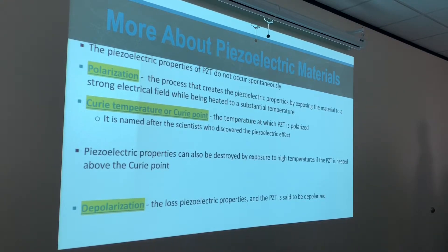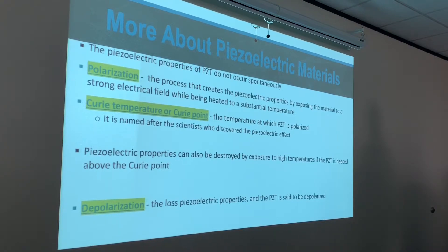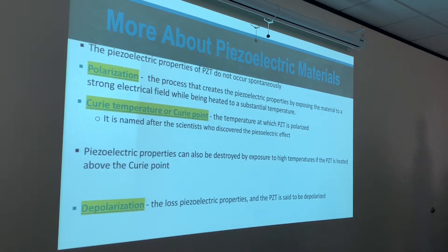Piezoelectric properties can also be destroyed by exposure to high temperatures. If the PZT is heated above the Curie point, the PZT becomes non-functioning — that's why we're not allowed to put transducers into an autoclave. An autoclave is what's used to clean surgical utensils. Depolarization is the loss of piezoelectric properties — the loss of the ability to convert electricity to sound or sound to electricity. Polarization creates those properties; depolarization destroys them.